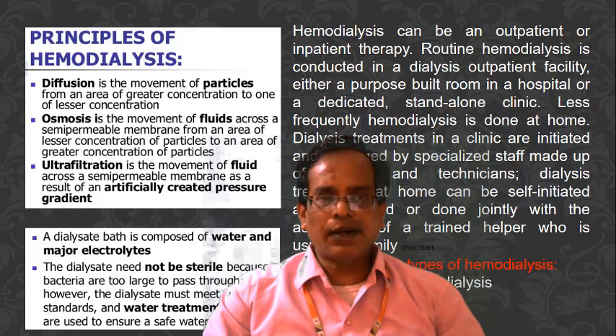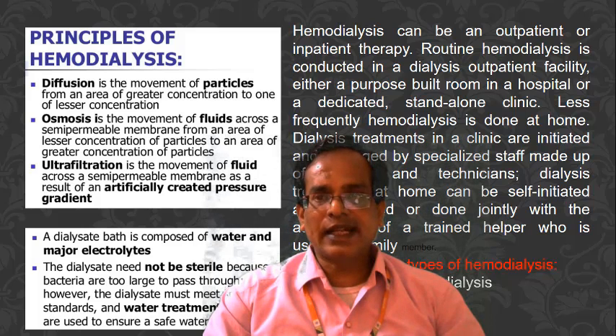A dialysate bath is composed of water and major electrolytes. The dialysate need not be sterilized because bacteria are too large to pass through. However, the dialysate must meet specific standards, and water treatment systems are used to ensure a safe water supply. Hemodialysis can be an outpatient or inpatient therapy. Routine hemodialysis is conducted in a dialysis outpatient facility, either a purpose-built room in a hospital or a dedicated stand-alone clinic. Less frequently, hemodialysis is done at home.